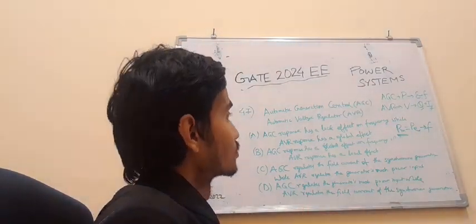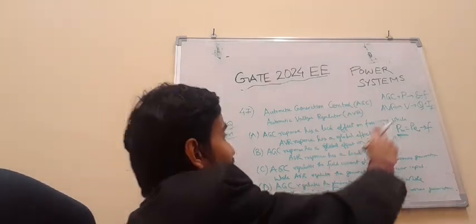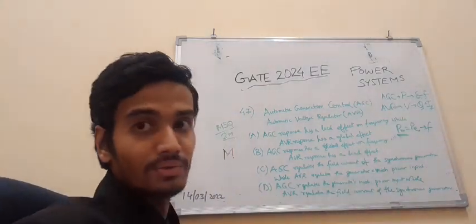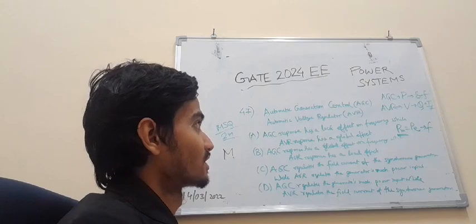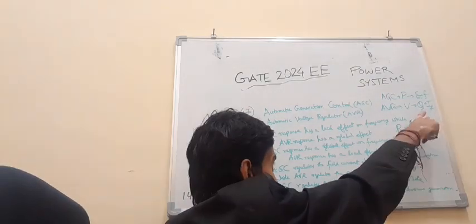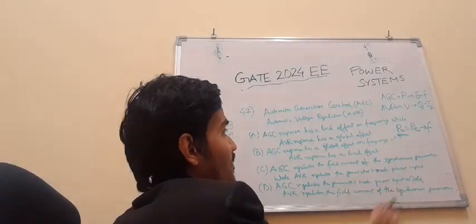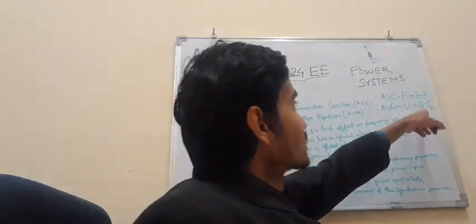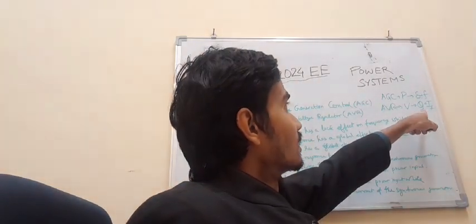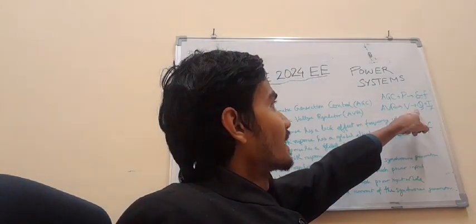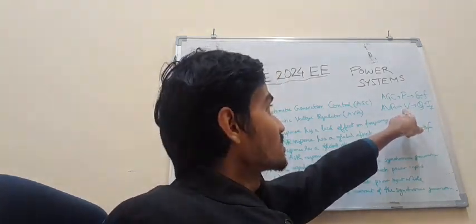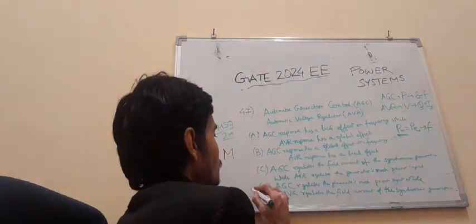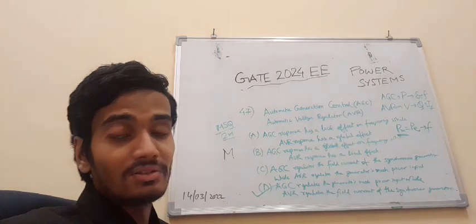And what does AVR do? It regulates the voltage, the terminal voltage, the excitation voltage of the generator. The excitation voltage depends on the field current. So it regulates the field current, which in turn regulates the reactive power, and as the reactive power is strongly coupled to voltage, it regulates the voltage. So this option is correct, as I have discussed.